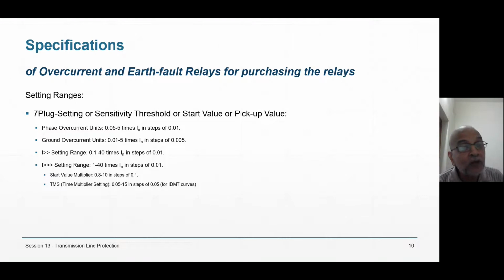So the numerical relay manufacturer gives a start value multiplier. It sees this starting current, because 10 times the current is not sinusoidal. It is highly distorted. So it reads the DC value, the subharmonics and the superharmonics, and based on it, it decides that this is a magnetizing inrush. When it is magnetizing inrush, if you have set the start value at 5 ampere, it will be multiplied by 0.8 to 10 times, whatever you want. Say 3 times, so it will be 15. So the relay will not operate.